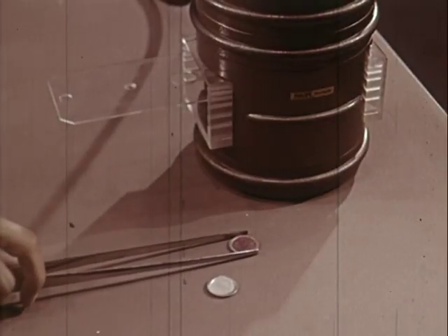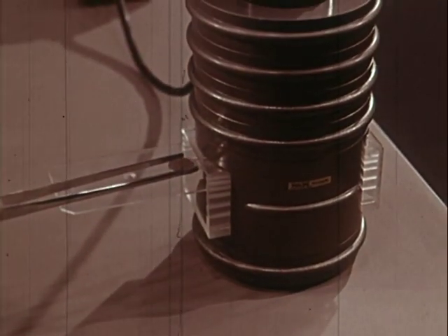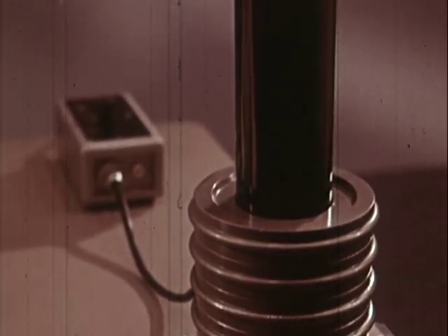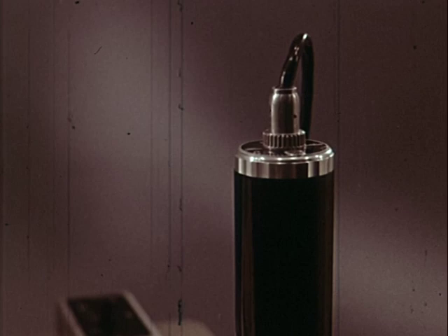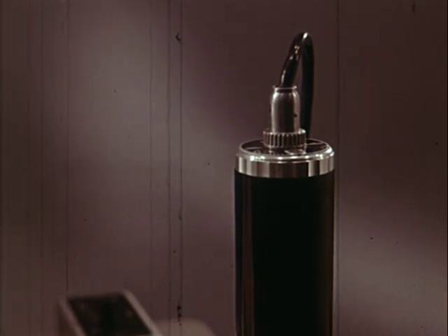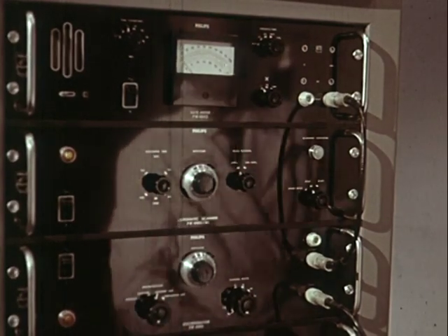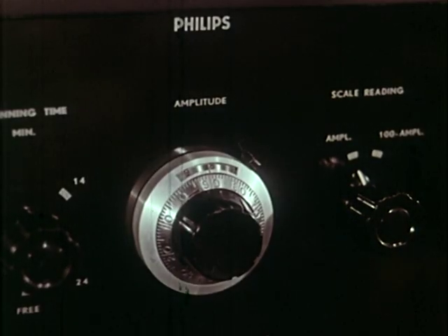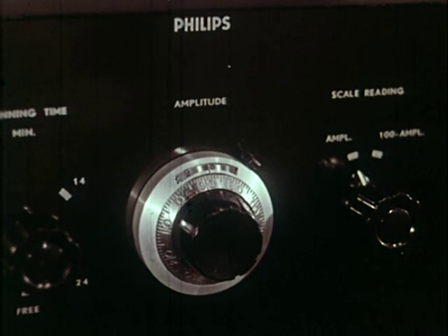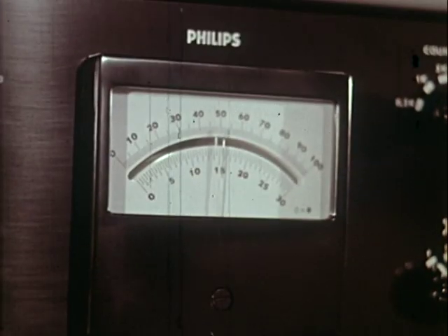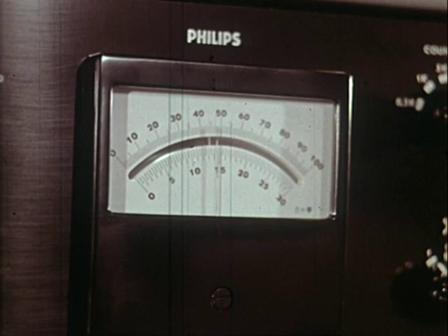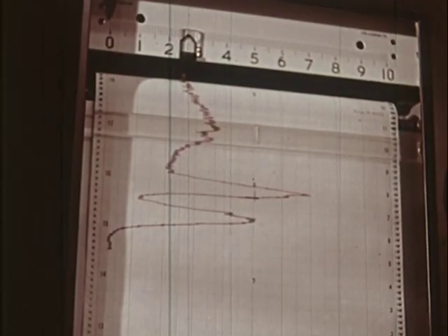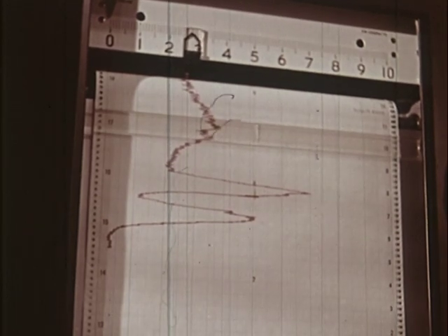The composition of a radioactive specimen is to be determined. The scintillation detector converts the emitted gamma energy spectrum into a spectrum of electrical pulses. The pulse spectrum thus obtained is then analyzed in the spectrometer. Energy levels are successively scanned. The count rate found on each energy level is plotted on a graph, resulting in a characteristic pattern of the isotope under investigation.